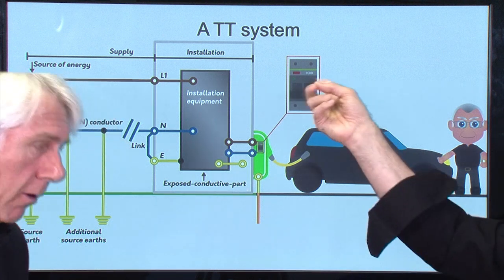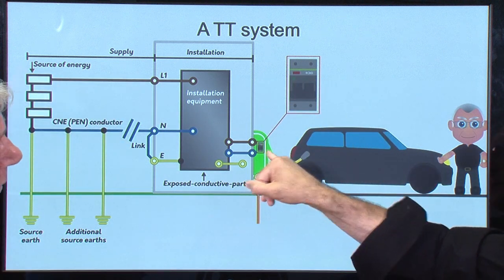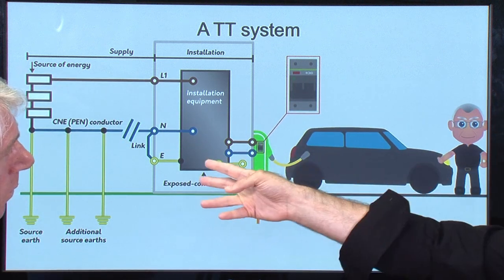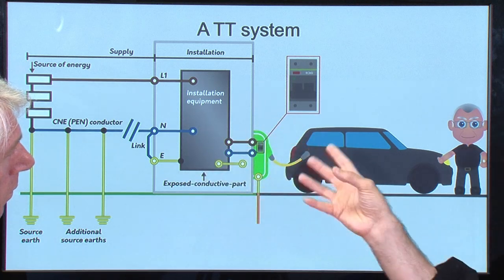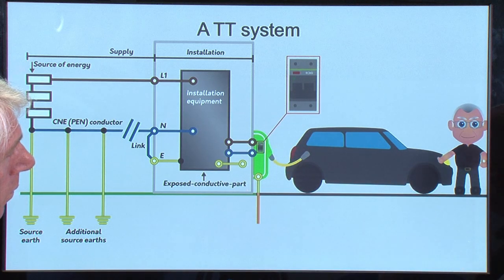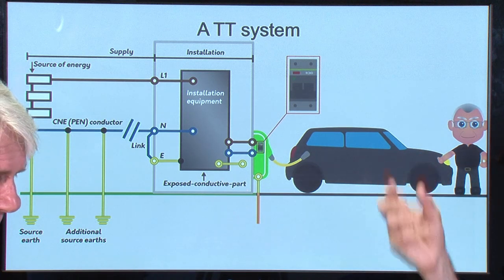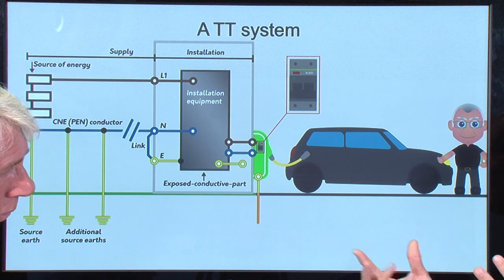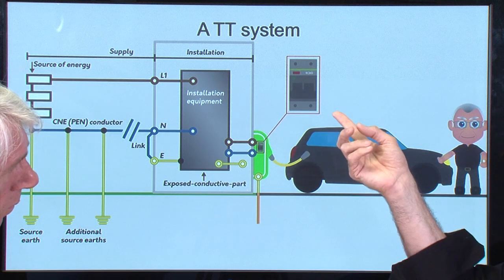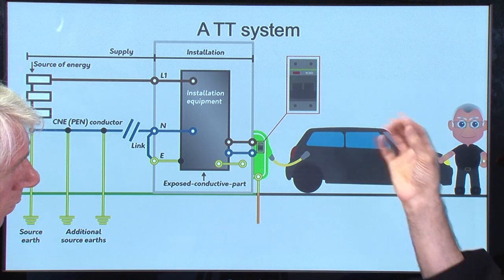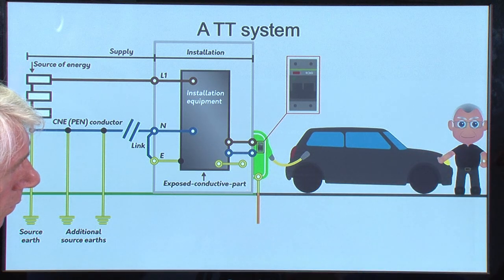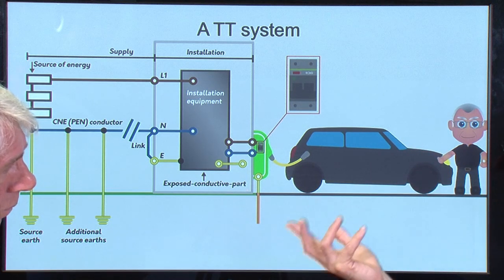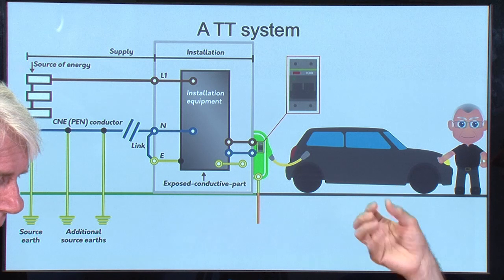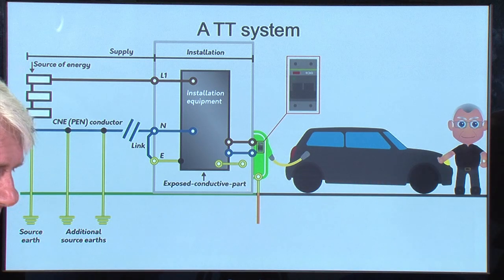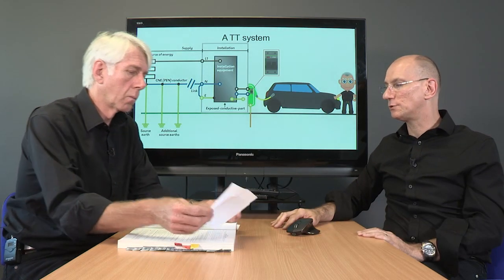Okay. Can I just talk about this? Because obviously what's not clear here is, because it's such a small graphic, is that we've got the overcurrent protection at the origin and in the charging point, and various manufacturers will have monitoring devices and protective devices and RCDs, MCBs, could be RCBOs, and I've seen various arrangements. This particular one would need to be, for the RCD, at least a type A or a type B, which is more expensive, and this is because of the DC current that could flood into it and you wouldn't get the protection. So that would be another subject for another day, I'm sure.